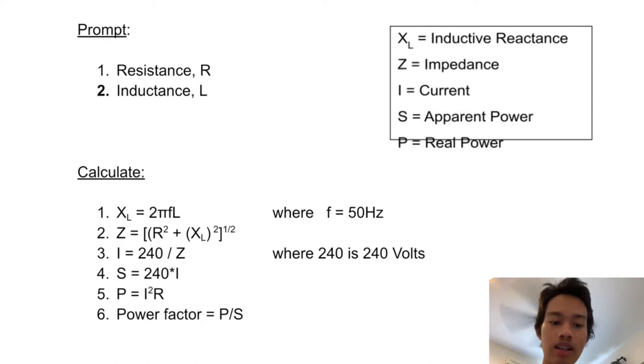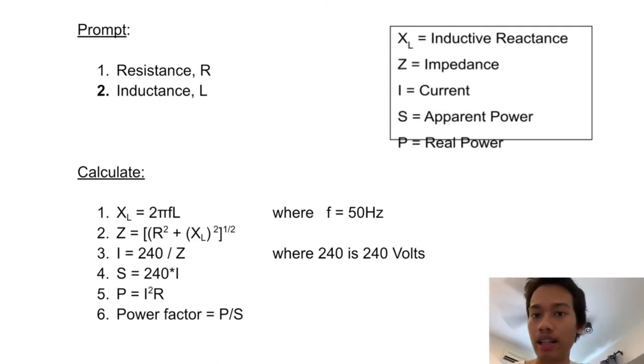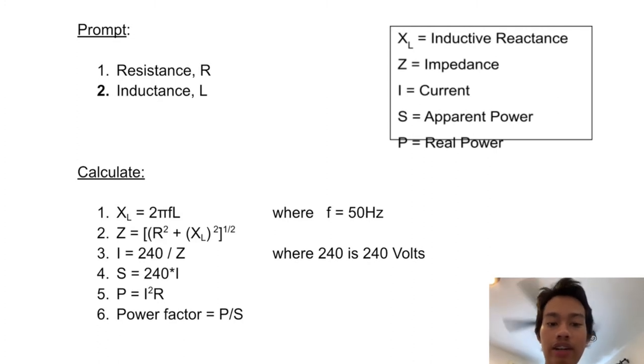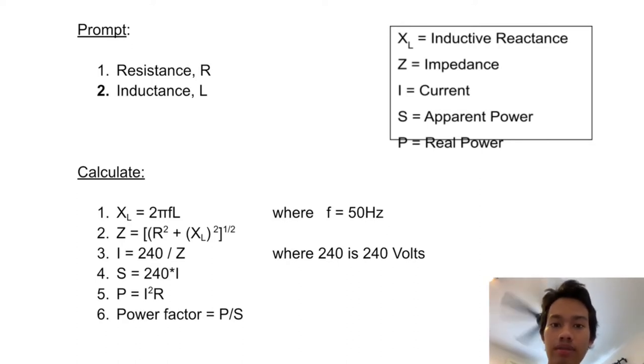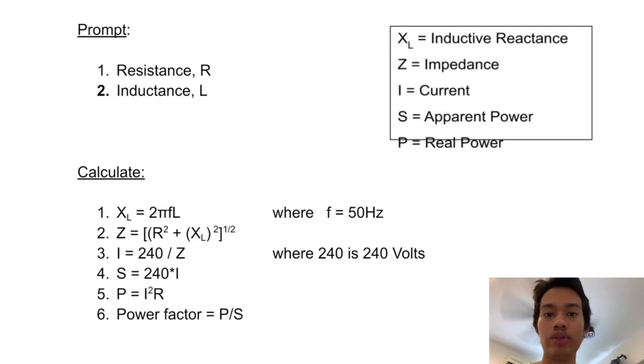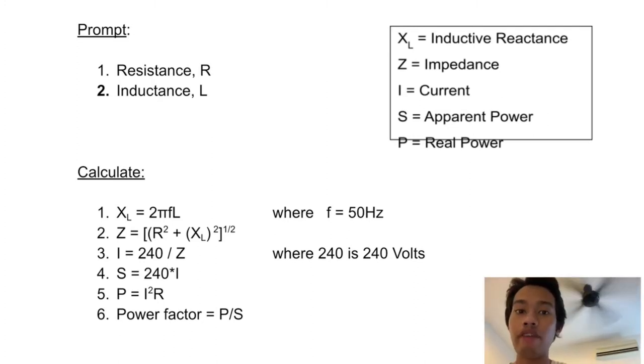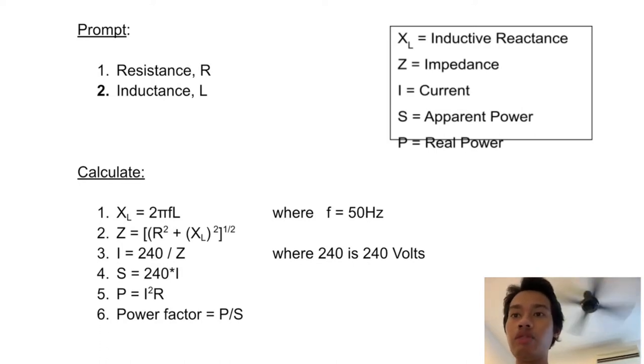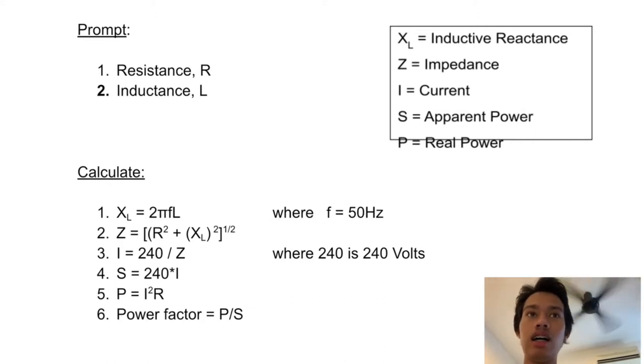In both cases, we use a frequency of 50 Hz and 240 V for our power supply, because that is what TNB supplies to our homes. Once we get the inductive reactance and impedance, we use them to calculate the apparent power and real power, and thus find the power factor for that particular house. With the power factor value, we can determine whether each individual house is efficient and decide whether power factor correction or an additional substation is needed.